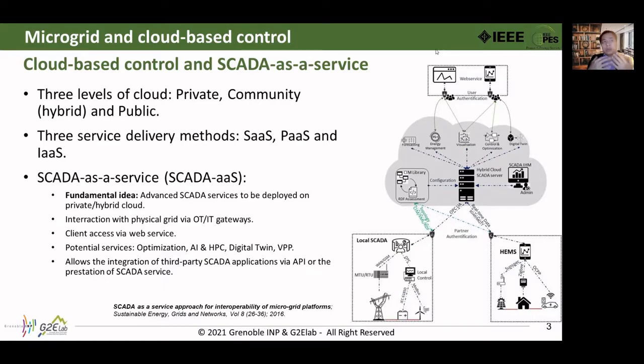Due to the reliability and security issues of an electrical grid in terms of response time and availability, critical control and protection tasks should be executed by the local PLC or RTU, and the exchanged information should be selected and monitored.